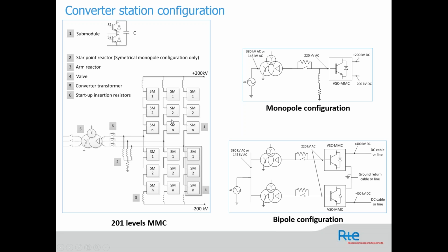So basically you will have at the end 6 arms, and then you have a star point reactor, which is used to have a reference to ground, and then you have a step-up transformer to connect the AC side to the converter terminals. Of course, you also have what we call here the startup insertion resistance. This is used only for the startup sequence of the converter.